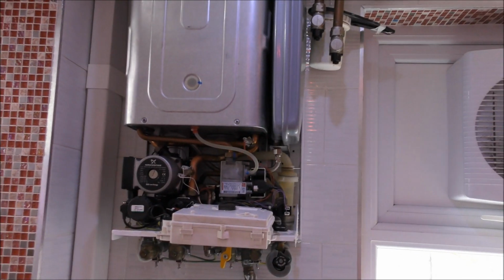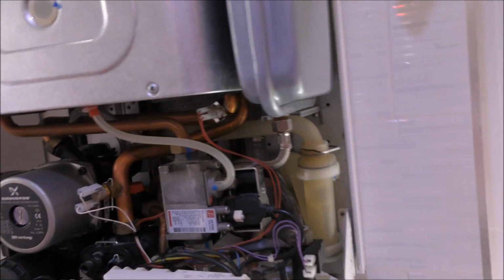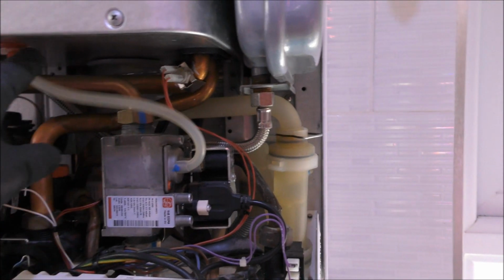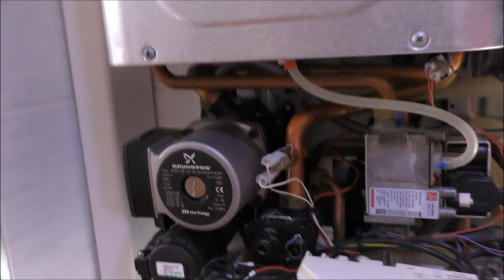Before moving on to the replacement of the thermistor, I've put the panel back on for the main heat exchanger, because this needs to be sealed properly, since there's a vacuum that goes into the gas valve from the exchanger unit. Make sure this is done properly. I wouldn't advise you to do this if you're not technically minded or a qualified gas engineer, but see how this has gone in - that's how the case needs to go back on, and the same applies on the inside.